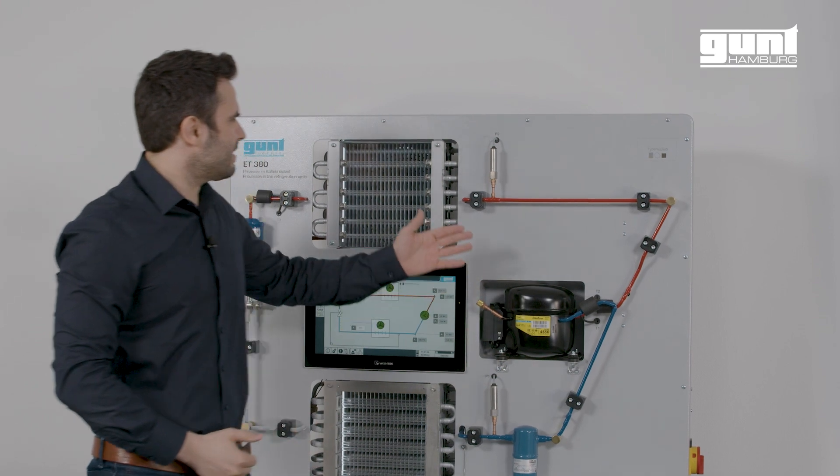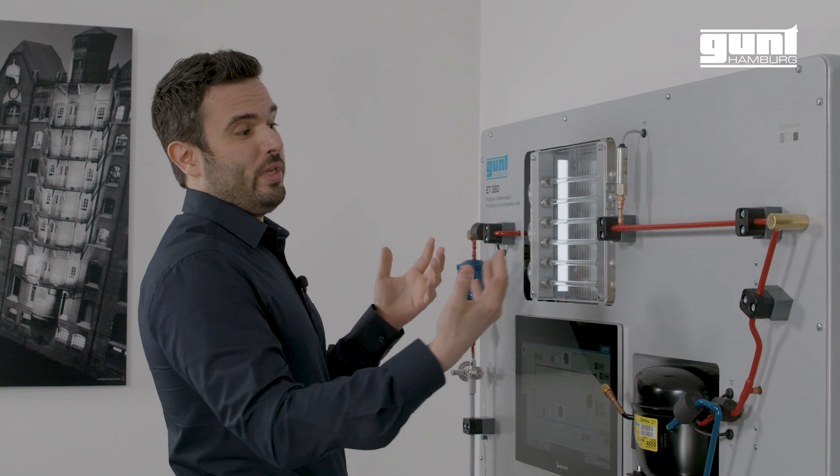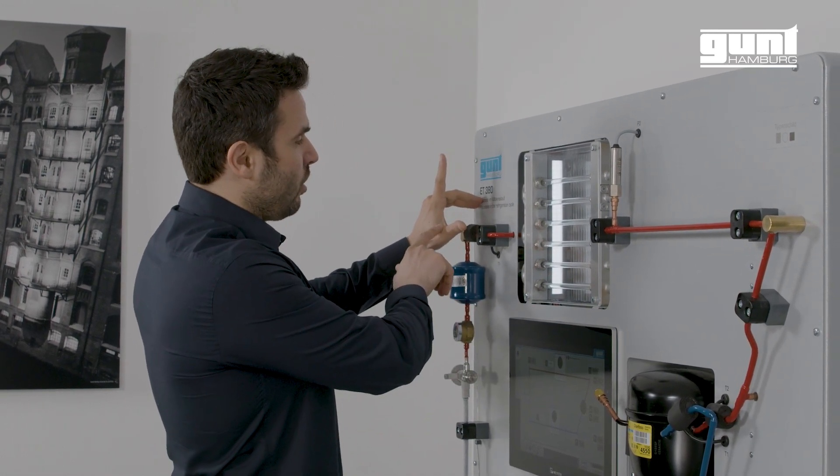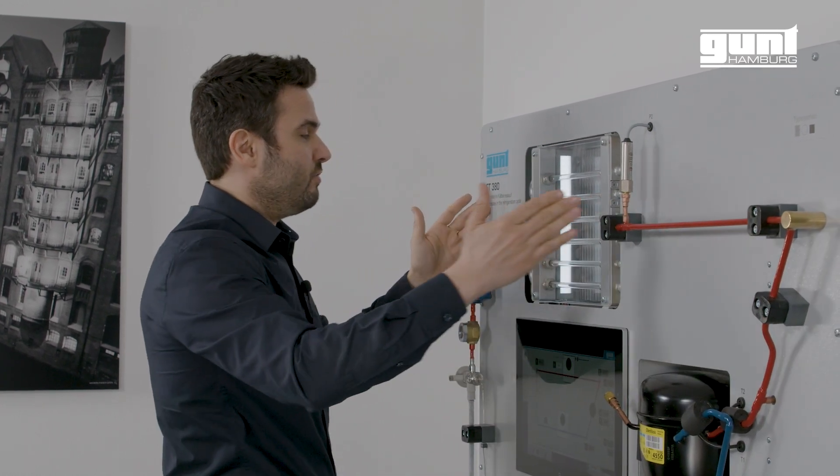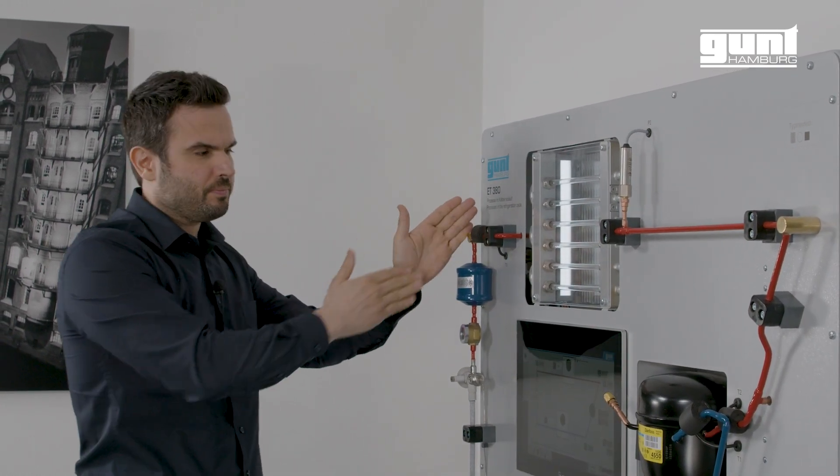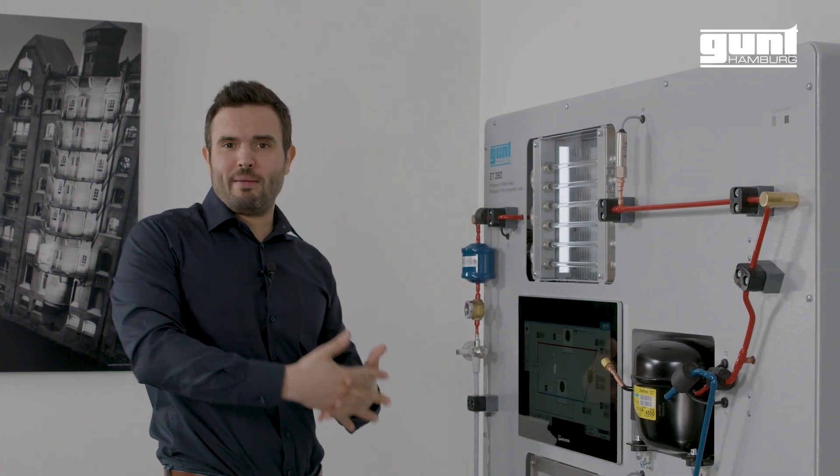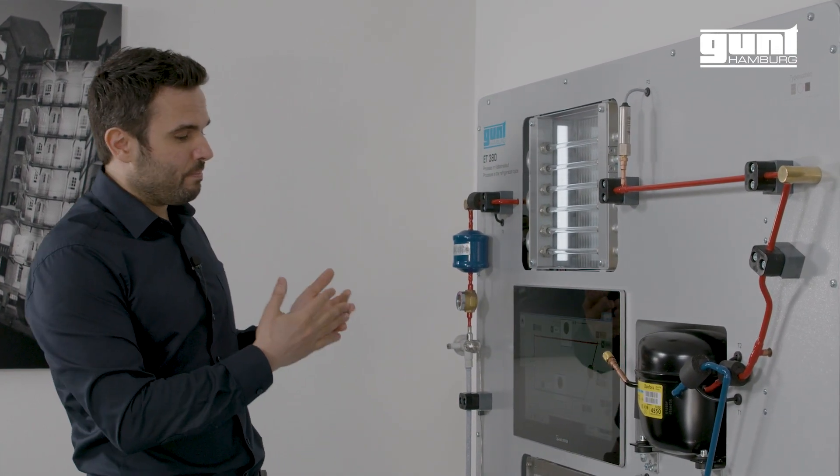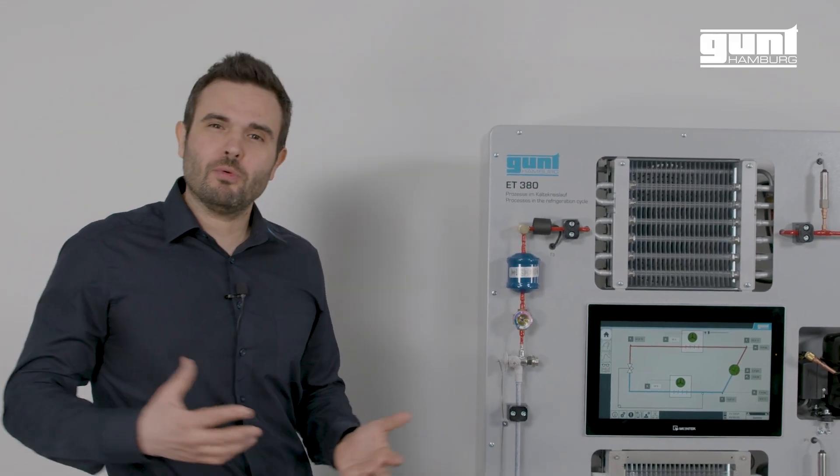In the next step we have a look at the condenser where all the heat is released, and what we can see is that the condensation takes place at a constant pressure level and the specific enthalpy drops back to its initial level. To make the liquefied refrigerant evaporate again, we make use of an expansion valve to bring the pressure back to the evaporation pressure. Interestingly, the specific enthalpy remains constant.